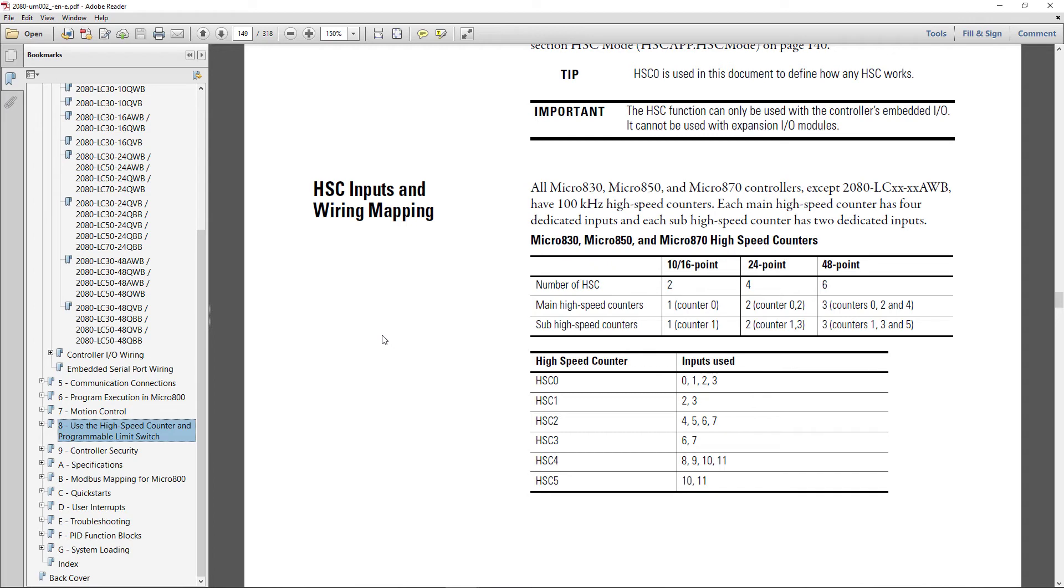And you see that there are six high-speed counters. If you look down below the inputs used, you'll see that high-speed counters 0, 2, and 4 use four inputs. High-speed counter 1, 3, and 5 only use two.